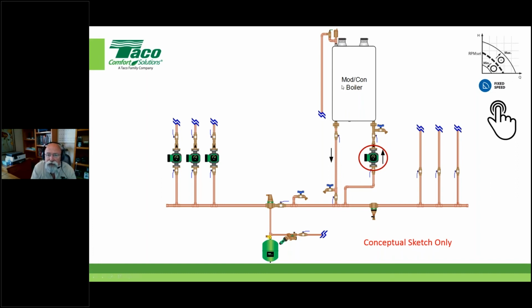But what we're saying is there's nothing within this circuitry—if you look at it, there's the boiler's heat exchanger, some piping, a T here—that's the circuit this circulator is responsible for. There's nothing that's going to give it a hydraulic change, an input to decide to speed up or slow down. So do not use an automatic mode for that pump; it just won't ever get the information to change its speed. It may or may not be enough. Now, I'll show you one application where we'll say go ahead and do this, but only once you've dotted your I's and crossed your T's. It's being done successfully, but it doesn't make sense if your expectation is that the pump will speed up and slow down, because it will not.